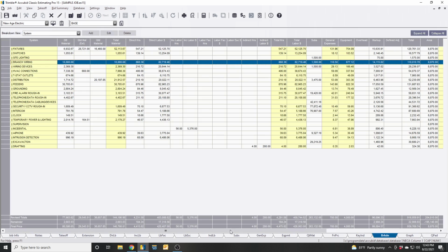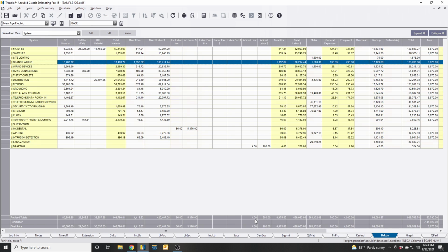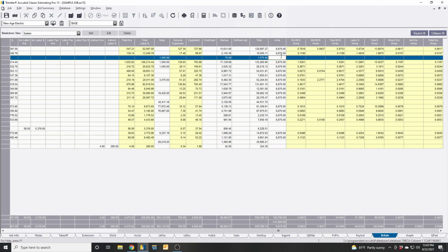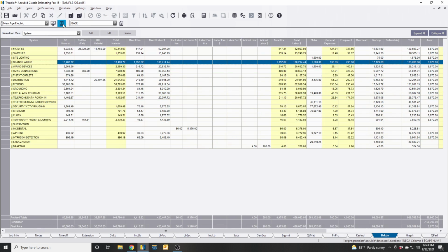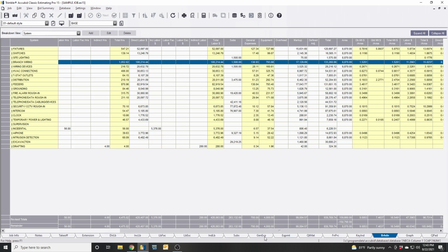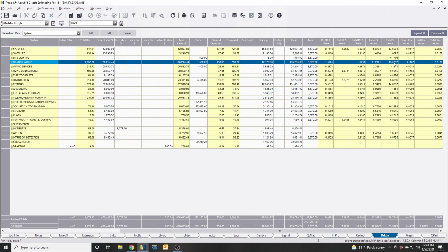Well, when you go in your breakdown, right click and reload. Make sure everything goes back here. Sometimes this happens. And let's now go in your branch wiring. Let me change this view, the reporting view, so this gets locked in place. Now it's saying that my branch wiring is $15 per square foot, which is extremely high.